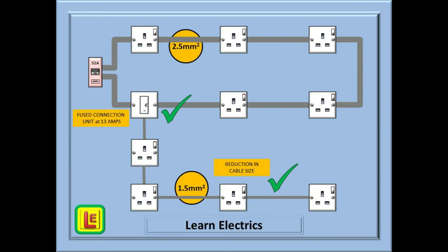Here we have the same ring circuit in 2.5mm twin and earth cable and still protected by the 32 amp breaker. We have replaced a socket with a fused connection unit, sometimes called a fused spur. But we could just as easily have made this FCU a spur and left the socket in situ. This is the important part now. Because the FCU has a 13 amp fuse, we can't exceed 13 amps for everything that follows afterwards.